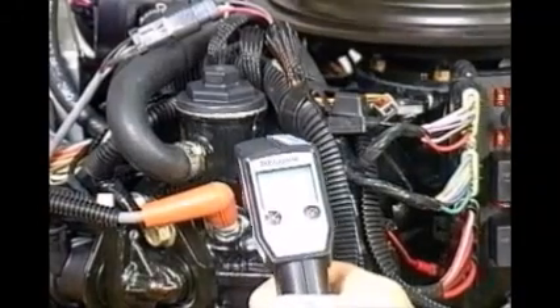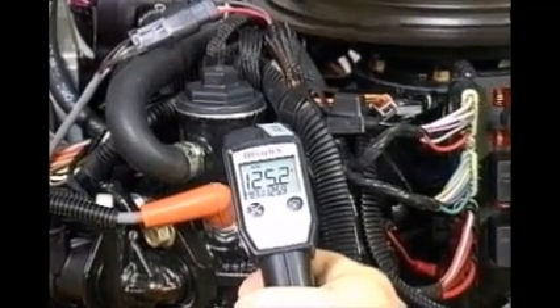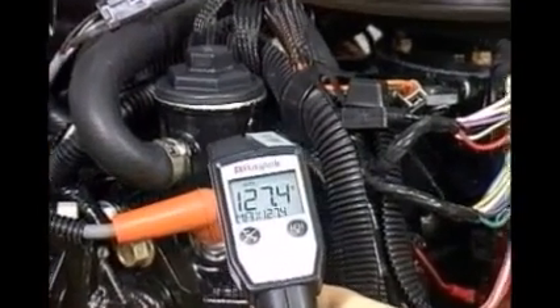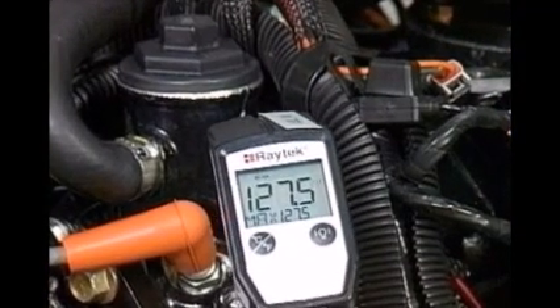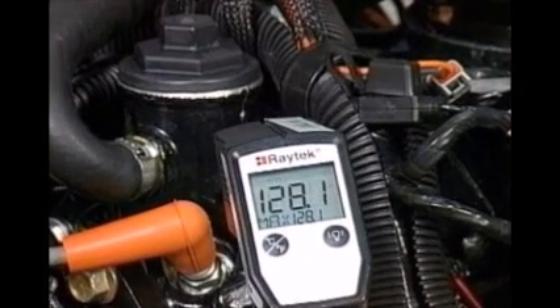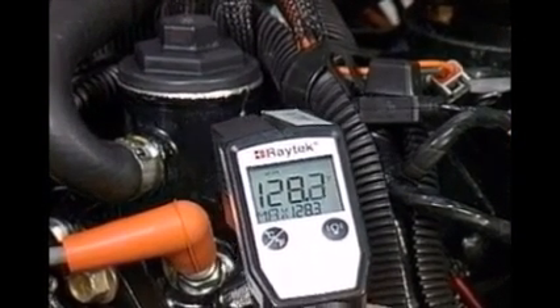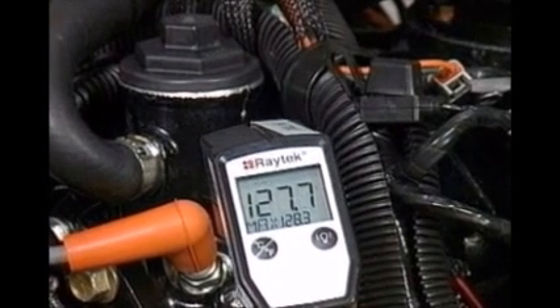The service manual describes where to take a temperature reading. It will also specify a temperature range at idle and a maximum temperature at high speed. There is no minimum temperature specified at high speed.